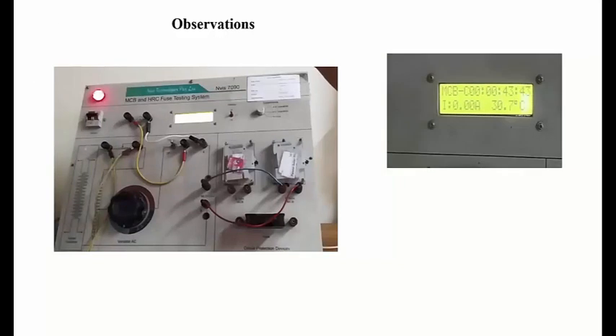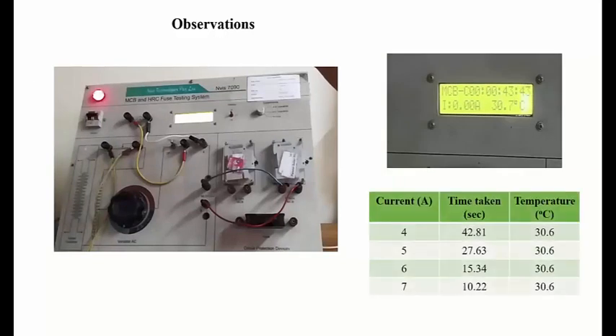The MCB trips at 42.81 seconds. Likewise, we'll be taking different sets of readings for different values of current at 5 ampere, 6 ampere, and 7 ampere. We observe that the time the MCB takes will reduce.